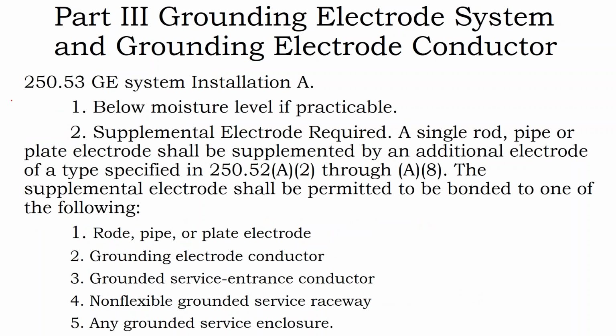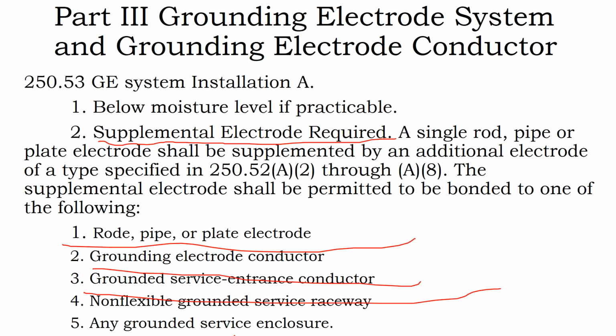So then we get into not just your grounding electrode, but a supplemental grounding electrode. And what's that? Well, you need an extra one just in case. Supplemental ground rod required, and it's required when you're required to have a supplemental electrode. A common way is to take your existing ground rod and then drive another ground rod right next to it and bond them together. Or you could connect it to your grounding electrode conductor or a grounded service entrance conductor.